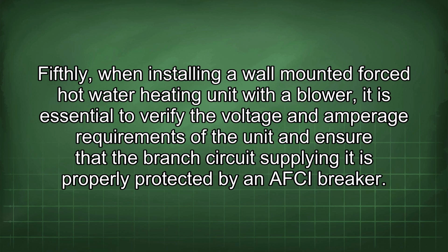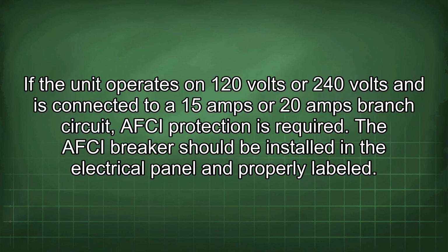Fifthly, when installing a wall-mounted forced hot water heating unit with a blower, it is essential to verify the voltage and amperage requirements of the unit and ensure that the branch circuit supplying it is properly protected by an AFCI breaker. If the unit operates on 120 volts or 240 volts and is connected to a 15 amp or 20 amp branch circuit, AFCI protection is required. The AFCI breaker should be installed in the electrical panel and properly labeled.